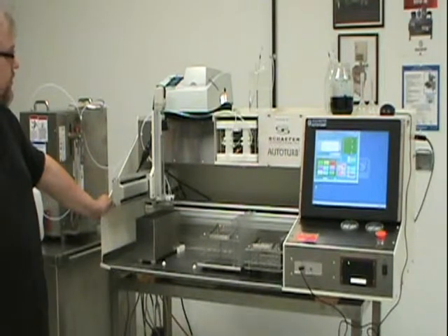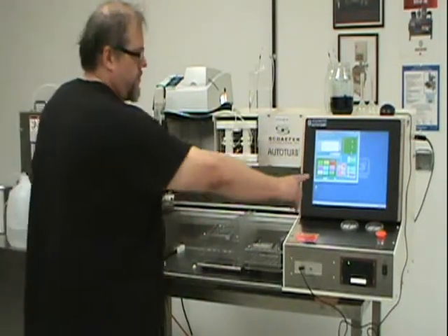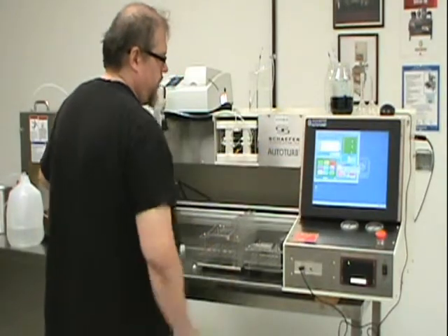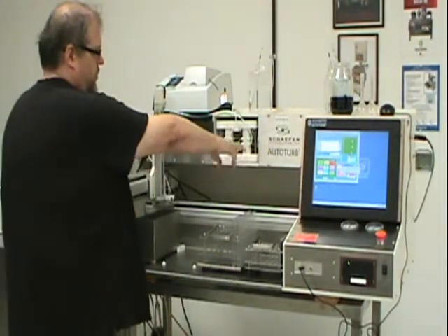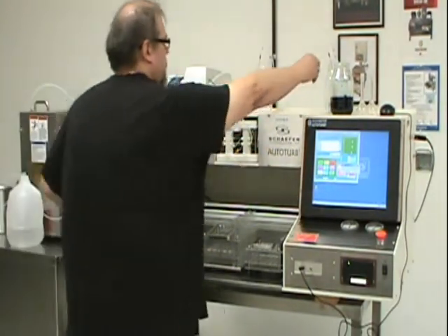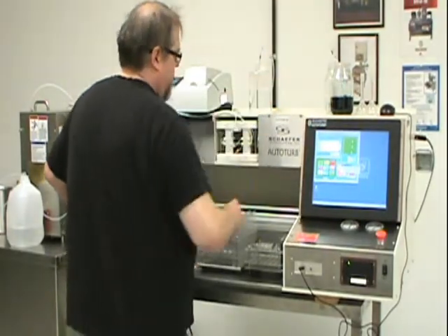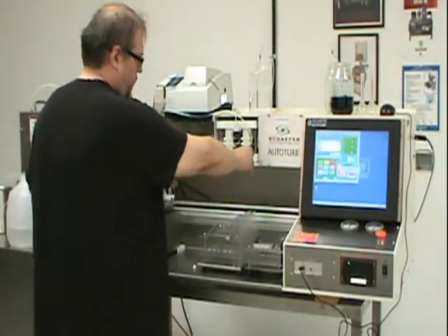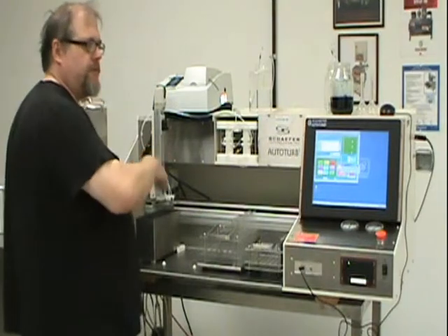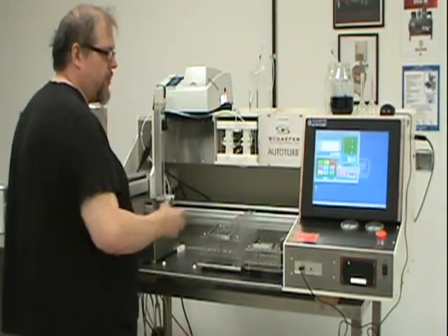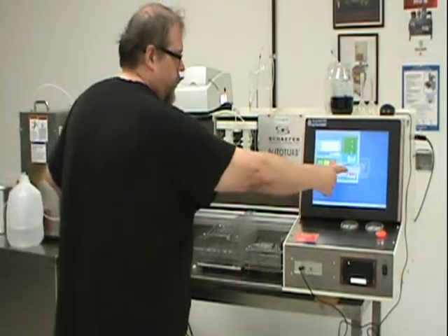Now, the first thing I like to do in a situation like this is to do a purge valve, which flushes fluid through the valve assembly. We use some blue dye to see that there's something going on here. Basically, what we're checking is to make sure that the valve is actually moving, that we have air pressure, and everything's good to go for that.